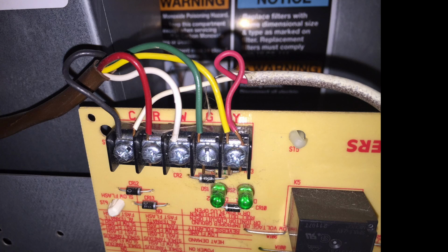The one on the right-hand side that has all the paint mess all over it, that is a 2-wire, and that comes from your outdoor condensing unit. It either is a 2-wire or a 3-wire, depending on the functions of it. When you're connecting your outdoor unit, remember, it's only designed for cooling. So one of them's going to go into cool, and it doesn't matter which color you use, as long as it corresponds to what you're doing outdoors. So it's one end that goes to cool, the other one goes to common.